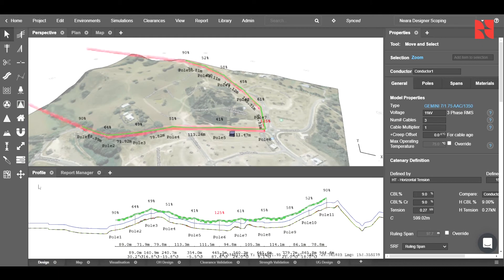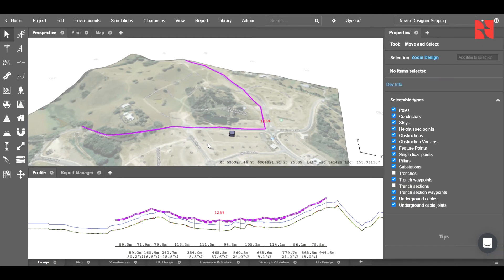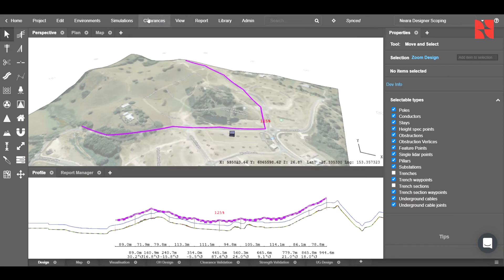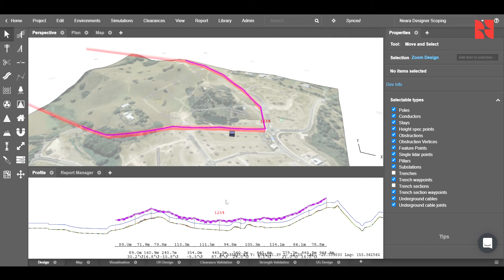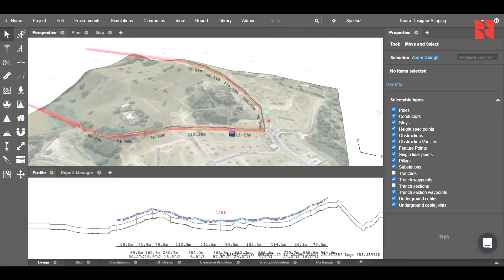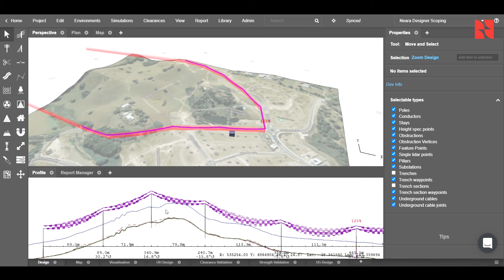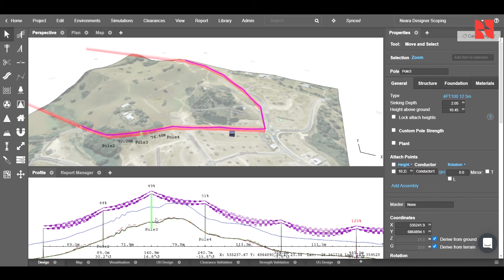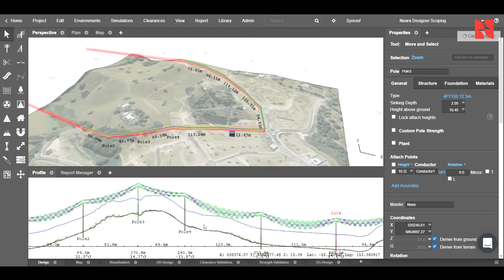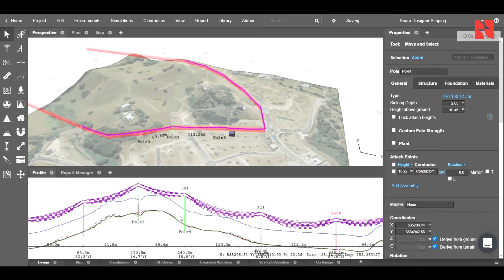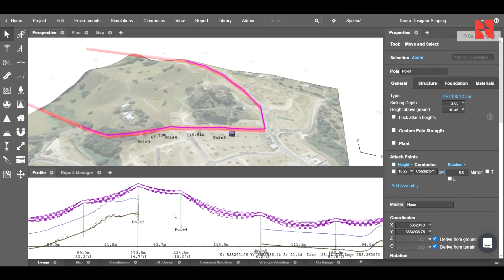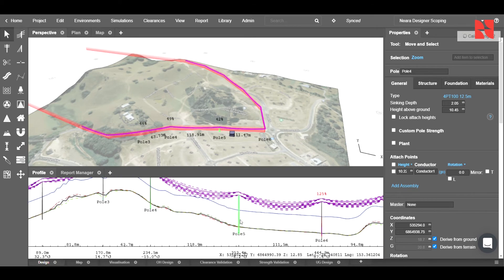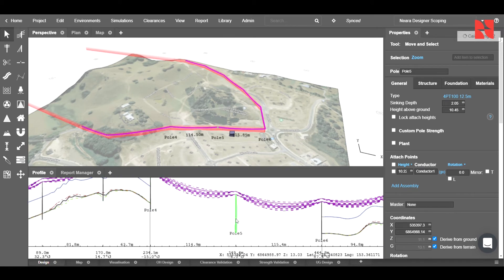Before we do that, we can look at our profile view to check our clearances. This can be changed by going into clearances and changing this line here. We'll leave it at 5.5 meters for now. We can go through and fine-tune the location of these poles to make sure that there are no clearance violations, with these bottom cables here showing the sag under our different environments.